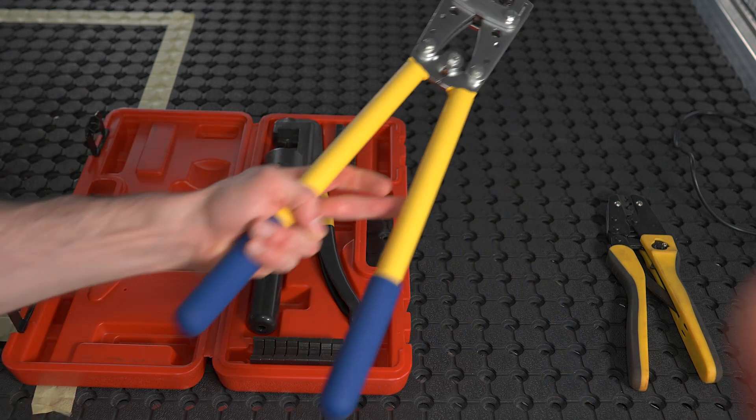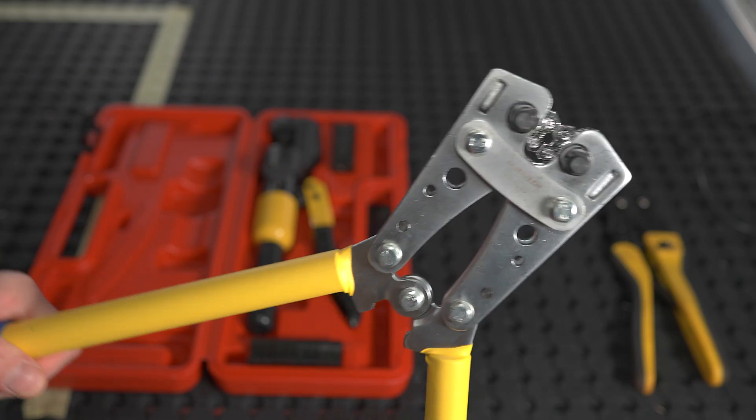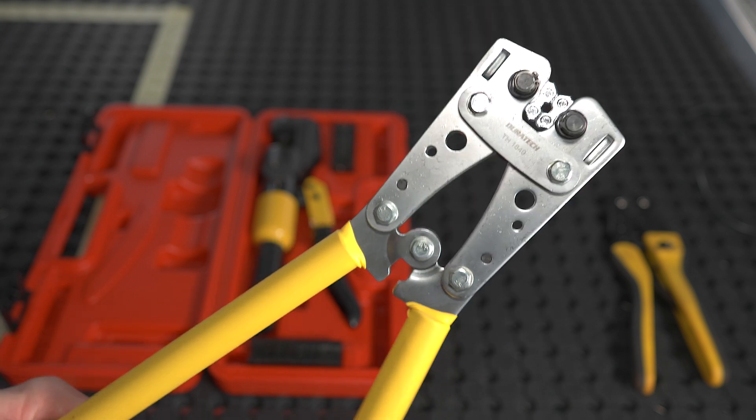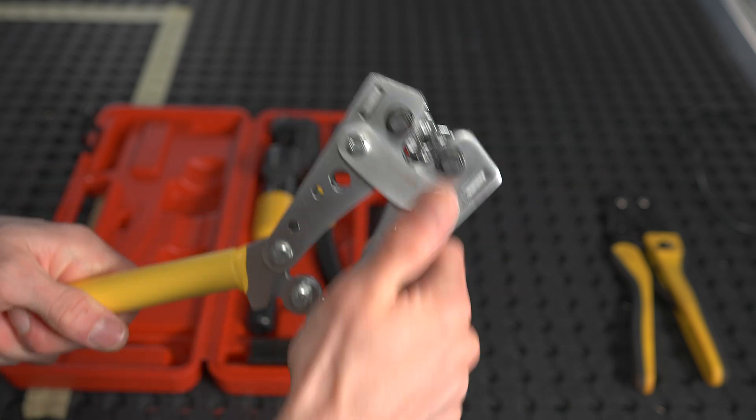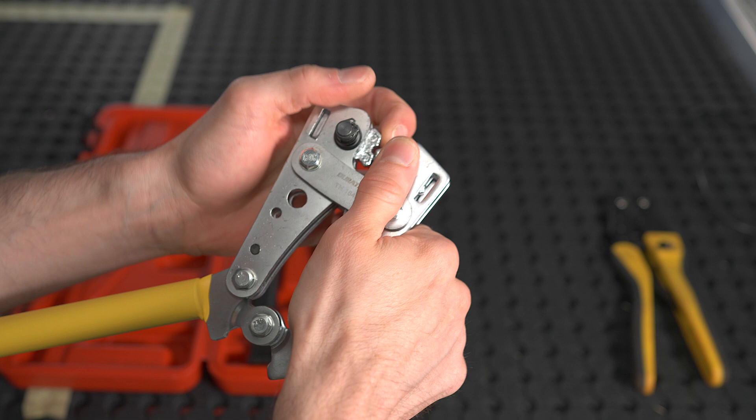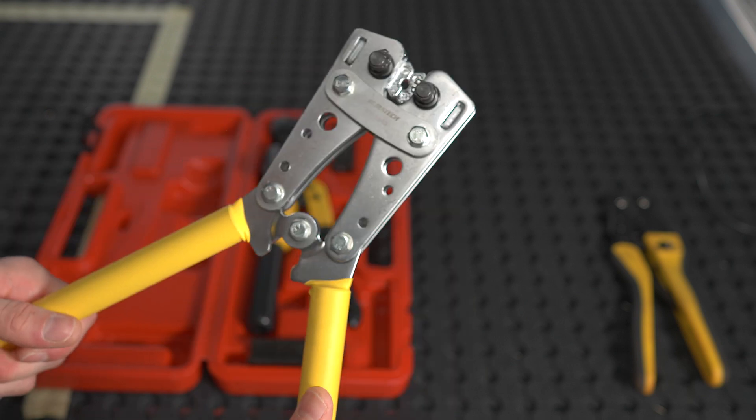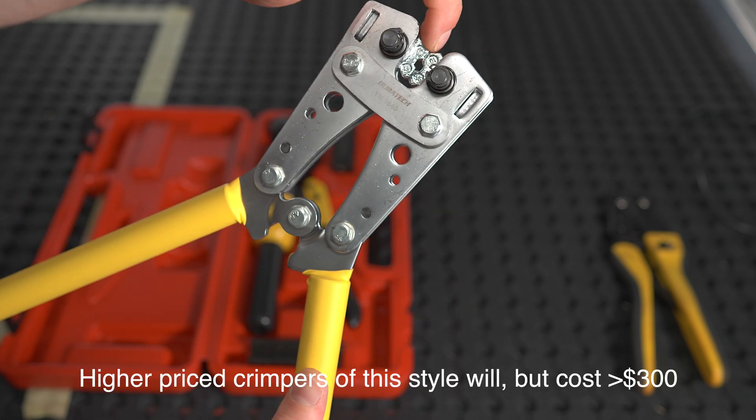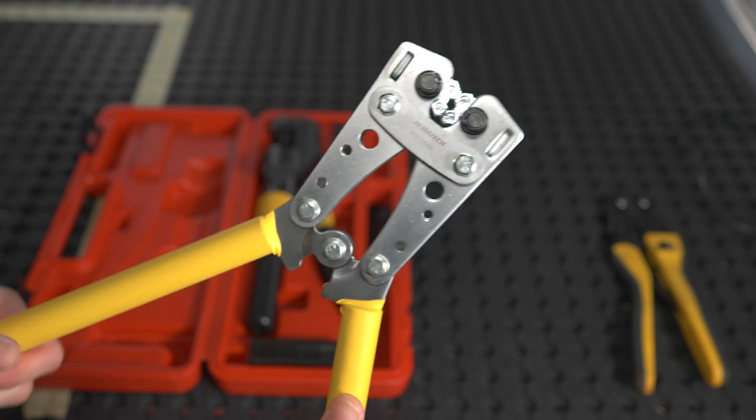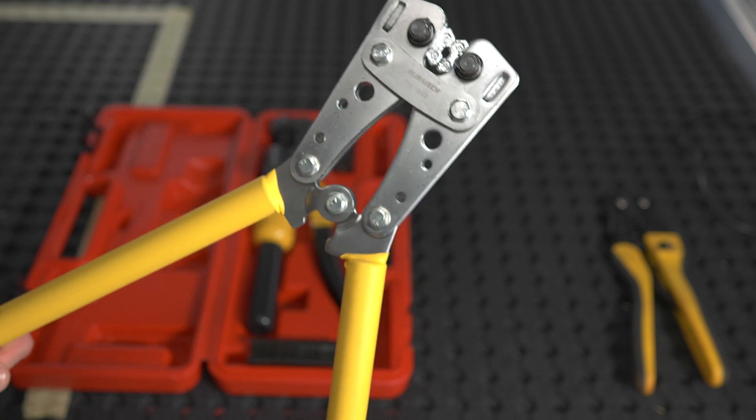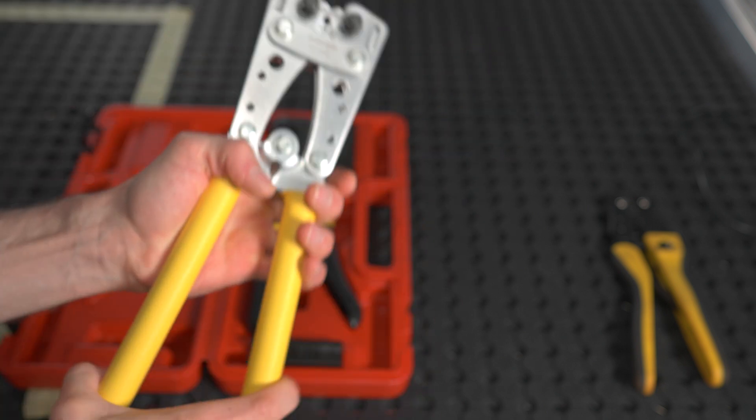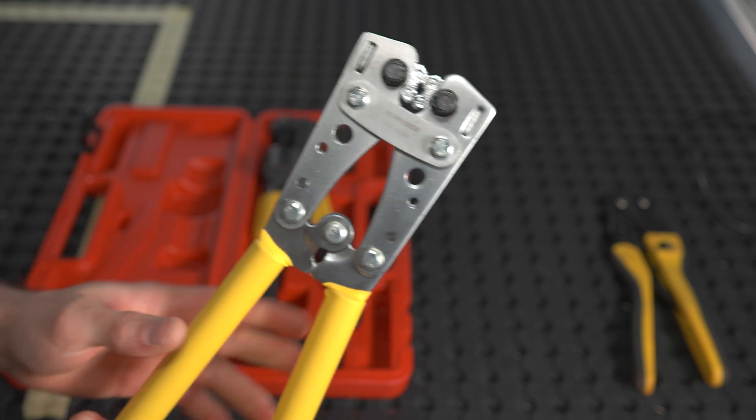This is a cheap pair of nutcrackers. The nutcrackers work the same except you use leverage instead of hydraulics. You have this die up here which rotates around for your different sizes. These do not leave a good crimp. These sizes to me are inaccurate, and you need to spend a lot of money to get a proper good pair of these. Spending $50-$60 on these won't get you a very good crimp and a really bad result.